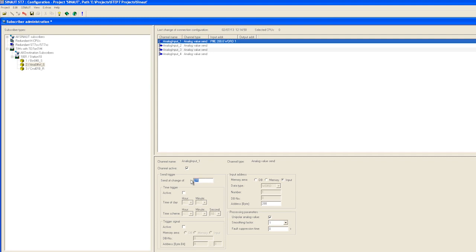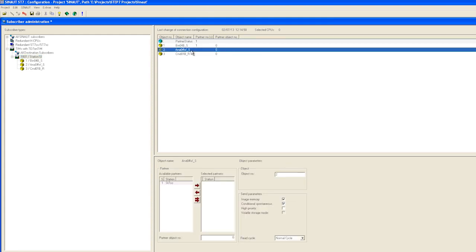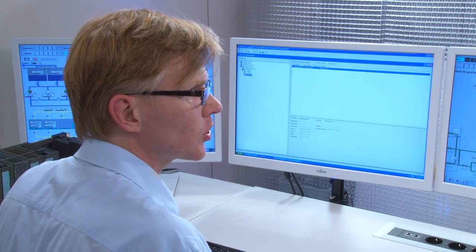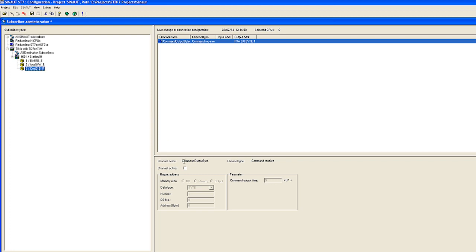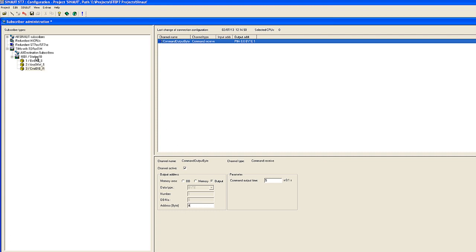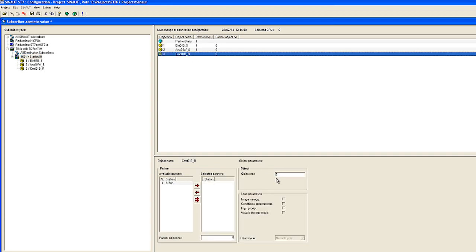Thus a value of 270 corresponds to 1%. Now we also address this block on the destination station number 1, and the remaining parameters are assigned like the BIN04 block. To do so, we activate another channel and specify a destination address to which the command will be output. In our case, directly to the digital output with output byte address 4. Here as well, we specify a partner, thus the command source from which the object originates, and an object number. This completes the configuration and we can now compile and load the project.